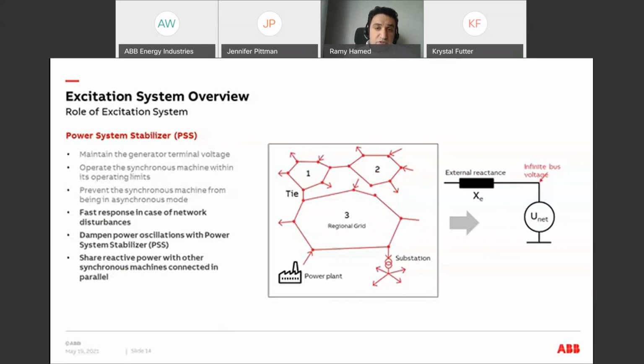We continue with the functions of the excitation. And now we move to the next function. So far, we talked about the generator as an individual unit. However, in reality, the generator is part of an interconnected grid with many other units and substations. And if an event happened on the grid, for example, a unit tripped or a short circuit happened, that event will affect the grid, and consequently, the generator in your plant will start to swing.